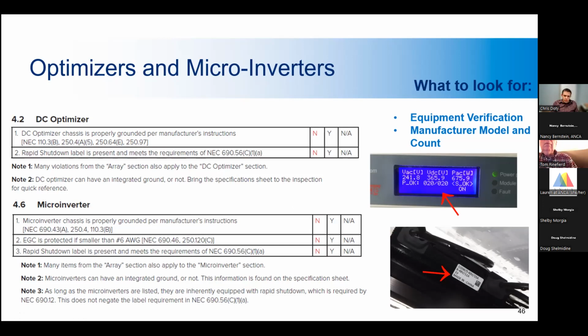The notes at the bottom describe important details such as the labeling requirements for rapid shutdown. Microinverters and DC optimizers are typically built with rapid shutdown requirements in their design. But one thing to keep in mind is they do require proper labeling, which we'll go over a little bit later.